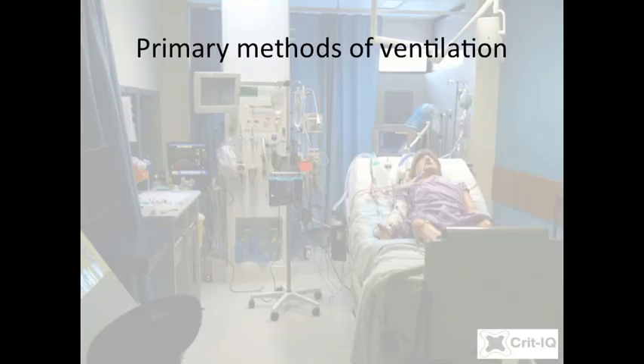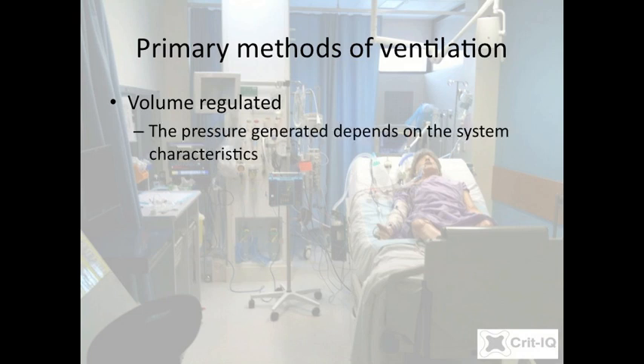In essence, ventilation is the delivery of a volume of gas to the patient's lungs, and then allowing it to passively flow out. There are two main ways of regulating this process. In the first, a ventilator pushes in a fixed volume of air, and the pressure generated is dependent on the characteristics of the system — including the ventilator circuit, the endotracheal tube, the lungs, and the extrapulmonary structures. This mode is known as volume-regulated or volume-cycled ventilation.